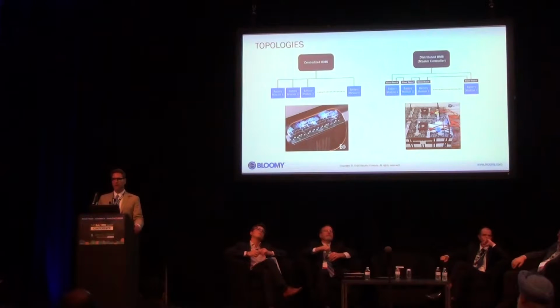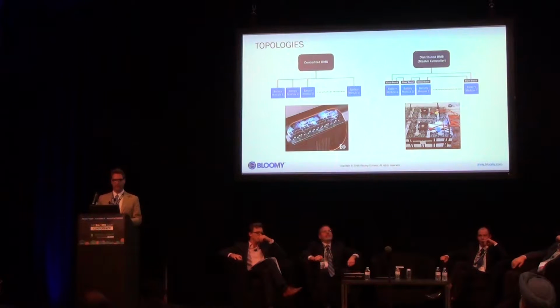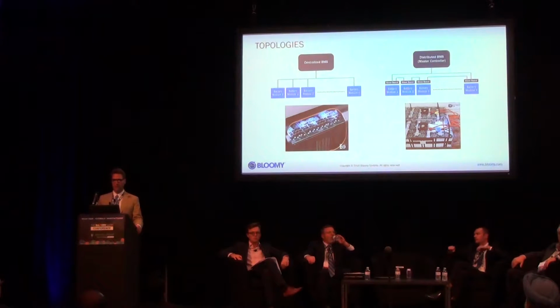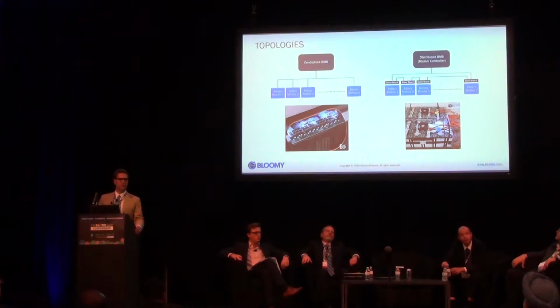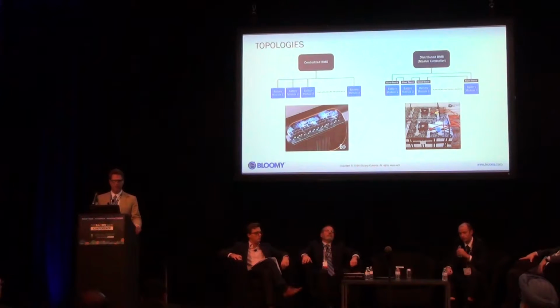So there are 2 main topologies of the BMS, and one of them is centralized. That's when you have one or a few PCBs that are centrally located that perform all of the BMS's functions. In the centralized architecture, you usually have a pretty significant wiring harness providing all of your cell monitoring and other wires up to all the individual cells from the central BMS. So the wiring is more extensive, more complex, more susceptible to noise, and also the BMS itself requires much more isolation because it's sitting on top of all of those cells.